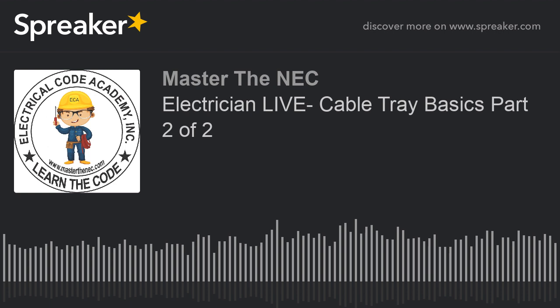you got to follow the rules for 392.22(A) for single conductors, for cables, and 392.22(B) for single conductors. You're going to have to come up with their allowable fill or their percentage of fill for each at this stage, in order to quantify that I can calculate the ampacity on each of them separately. And then follow the normal rules that we follow in 392.80(A), (A)(1), or (A)(2) accordingly, whether we're dealing with cables or single conductor.